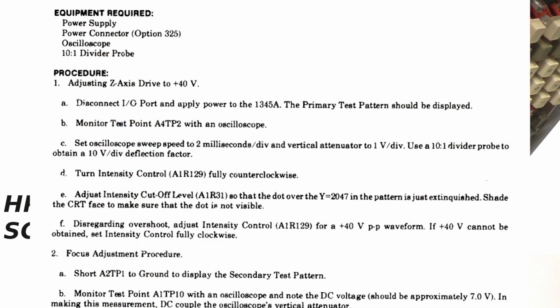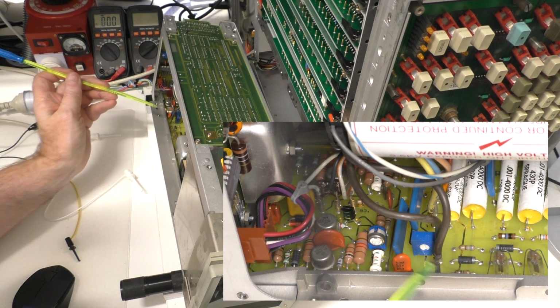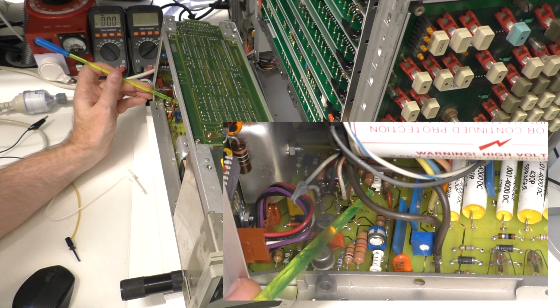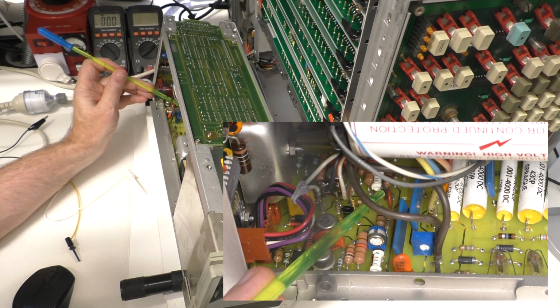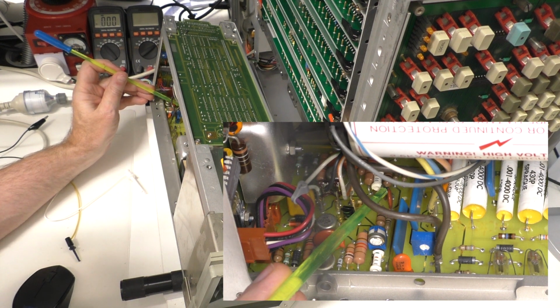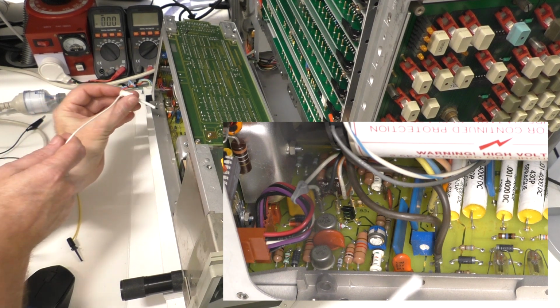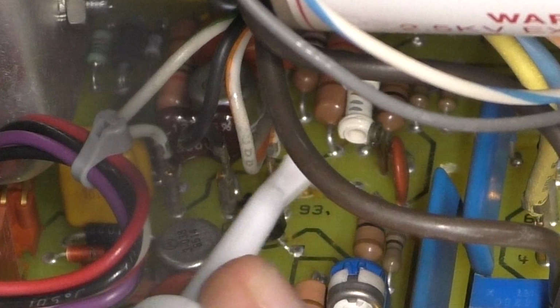5-16-1, adjusting the Z-axis drive to plus 40 volts. Note that this is an updated procedure documented in the 1985 revision of the service manual. Power down, and wait for supply to fully discharge. For this test we will attach a lead to the A4 high voltage board, put the display on its right side. Place a test cable clip onto test point 2.